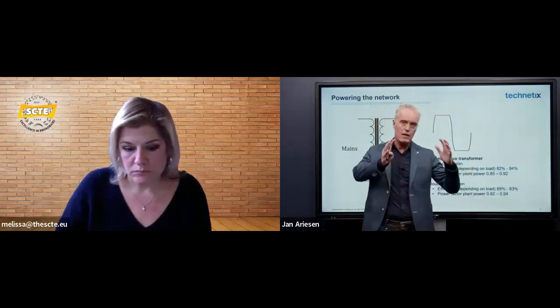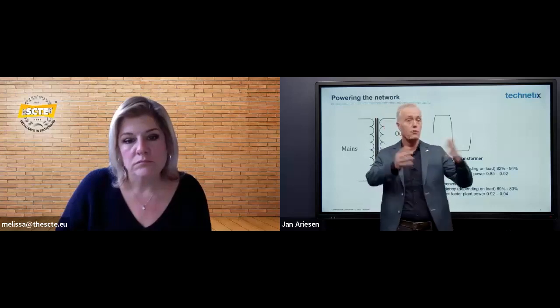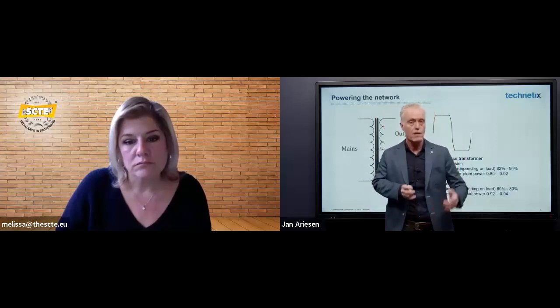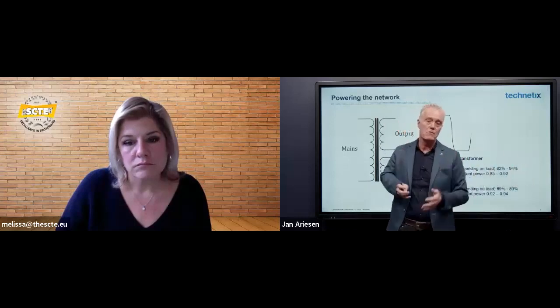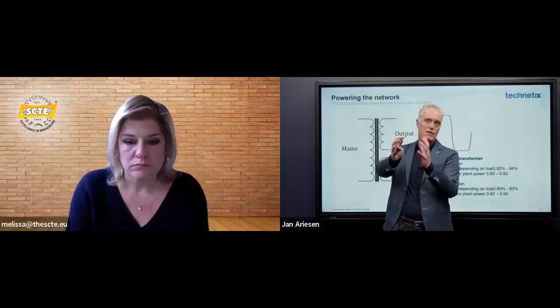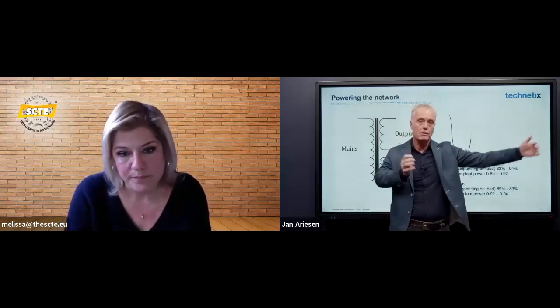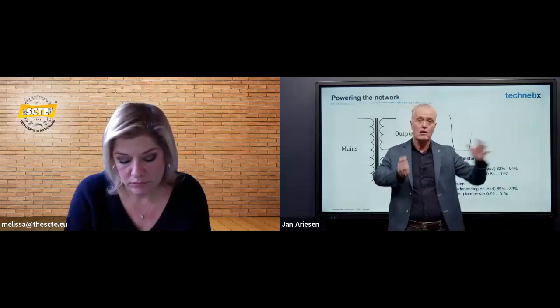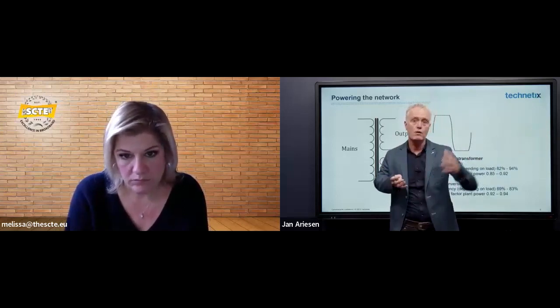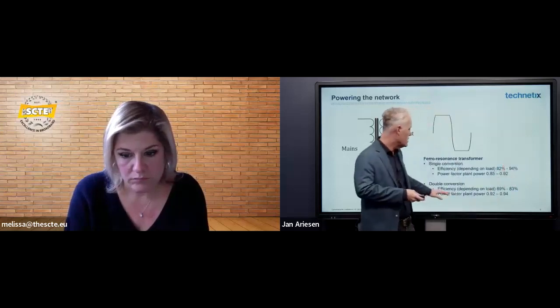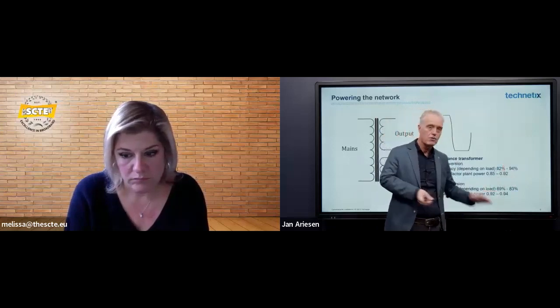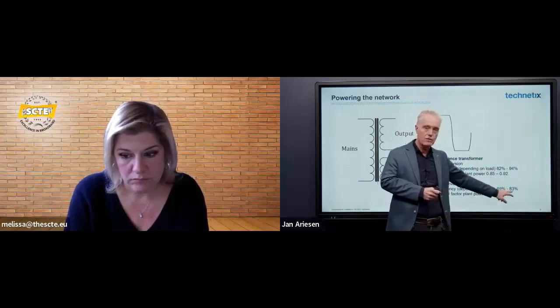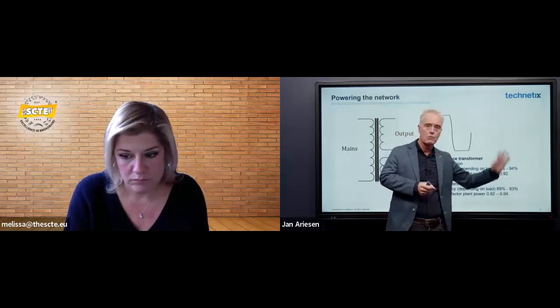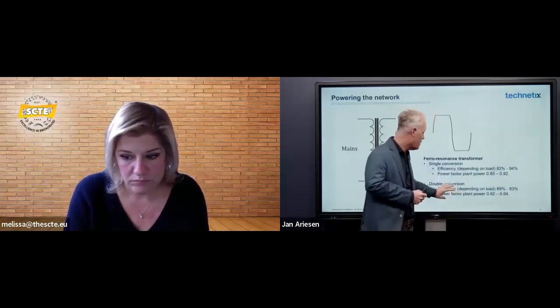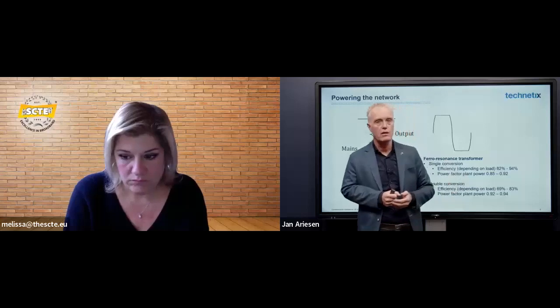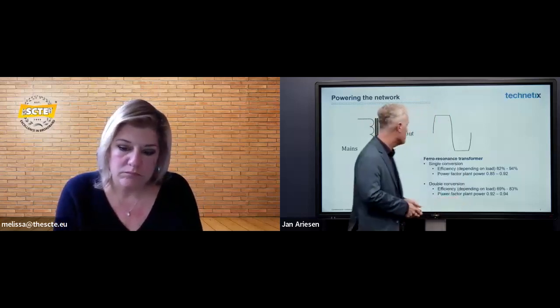As I said, you have that big iron pack that you have to magnetize. That will cost you 40, 50 watts or so to put in there. And if your network is only 200 watts, then you can imagine your efficiency is very bad, because you lose already 50 watts to deliver 200 watts in the network. If your network is 500 watts, the contribution of that 50 watts is, of course, lower compared to the whole network. So efficiency depends on the load, and it's somewhere between 69 and 83%. But your power factor is better. It's about 0.92 or 0.94. That's what you have with double conversion, and mostly double conversion ferroresonant transformers are used in the network.